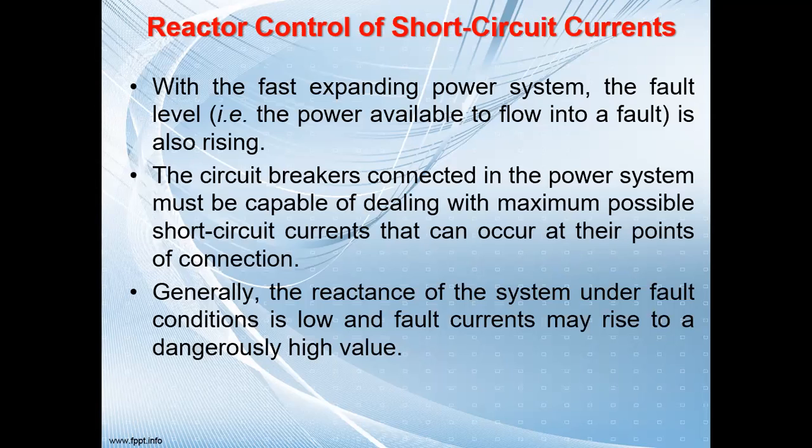And if you are increasing the load, and thereby increasing the fault level of the system, every time we have to change the circuit breaker. So that is not possible. If you change the circuit breaker, the cost will be involved. So now the solution is we can connect reactors into the circuit, and by connecting the reactors we can reduce the fault current, and we can use the same circuit breaker, and thereby we are reducing the additional cost of the system.